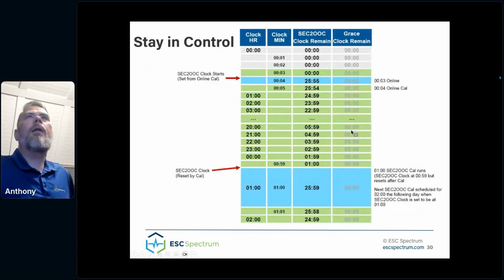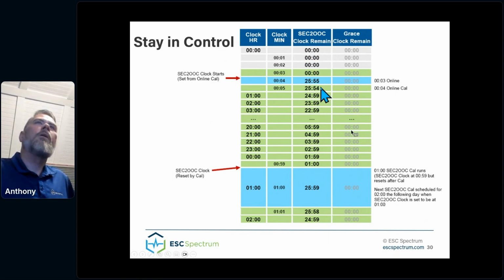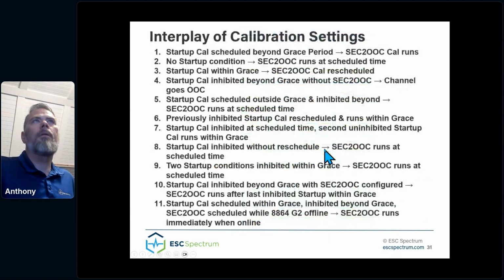Here's an example where we came online, an online cal was run to initialize and set all the counters. This was a brand new channel prior to this, which is why it didn't have any data. Again, gray is offline, green is online. And you can see that this just ran all the way until we hit 1 hour. The SEC2OOC setting on a calibration was set for 1 hour. When that occurred, this SEC2OOC cal kicked off and reset the timer to 26 hours later. And so theoretically, you could set up a SEC2OOC setting on your cal and you wouldn't have to program a digital event to kick it off. You just let it run whenever it wants.